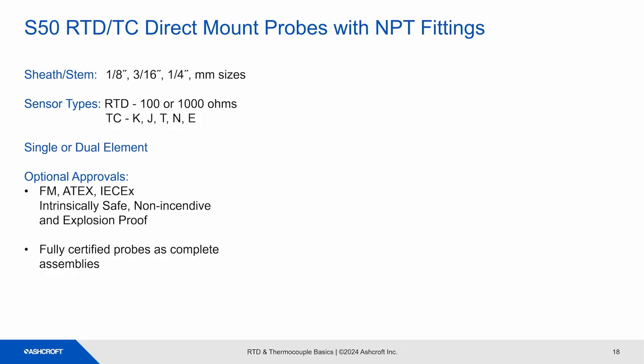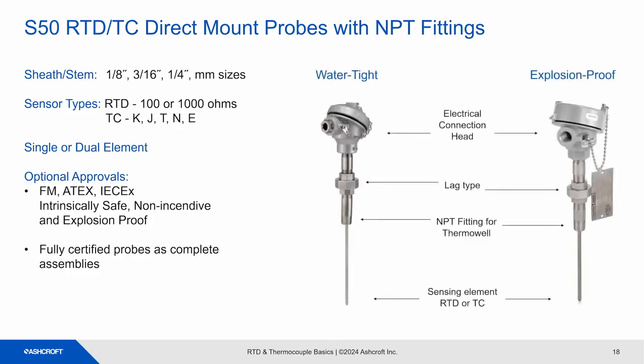The probes can have FM, ATEX, or IECEx approvals for intrinsically safe, non-incendive, and explosion-proof. The probes are fully certified as an assembly. They come in watertight or explosion-proof configurations with several head types available to meet many applications. We have many lag configurations. The lag length can be customized as well as the probe length.